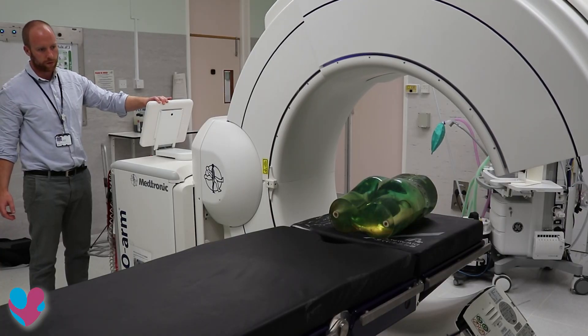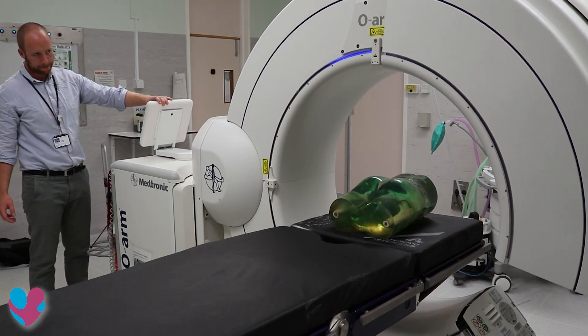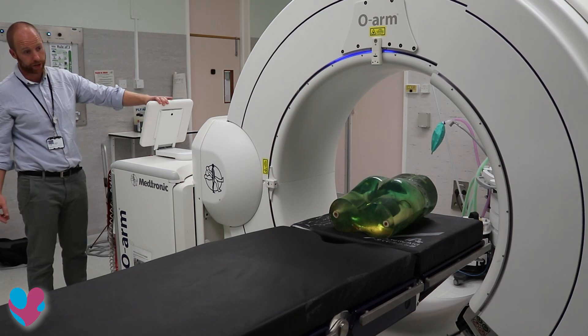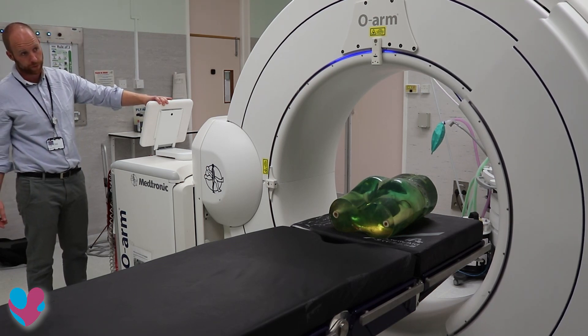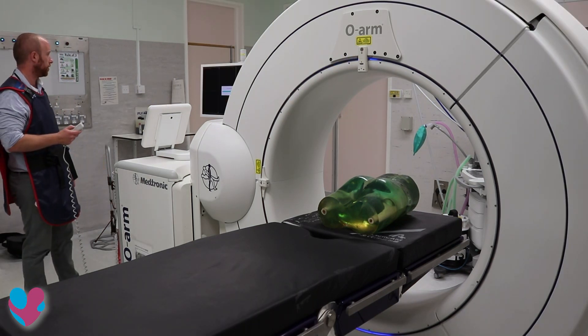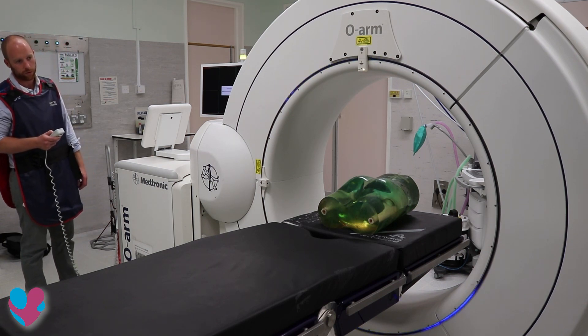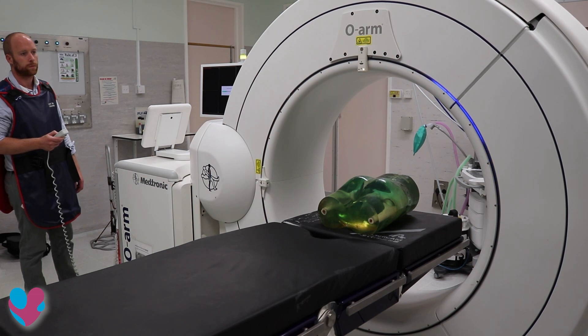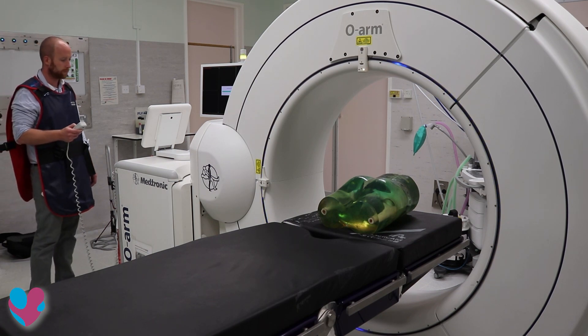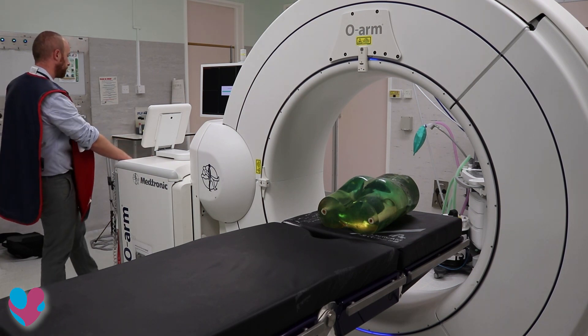The project centred on a mobile CT scanner used for paediatric scoliosis correction. This device has been shown to produce better surgical outcomes compared to alternatives for image guidance, but has the potential to deliver relatively high levels of radiation to the patient. To test a new protocol, Kenneth used a phantom dummy which simulates the impact of an x-ray on a real patient, imaged using the mobile CT scanner with images viewed by members of the surgical team. Based on their assessment of image quality, patient radiation exposure could be reduced by 80% compared to existing manufacturer recommendations.